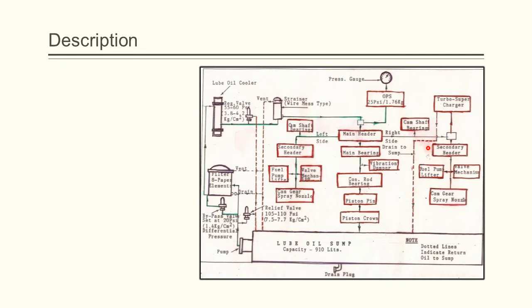The lubricating oil pump mounted on the free end of the engine draws the lubricating oil from the engine sump and discharges it into the system. The relief valve at the end of the discharge side of the pump protects the pump from high pressure and controls the discharge pressure at 105 to 110 psi by passing a portion of oil back to the sump.